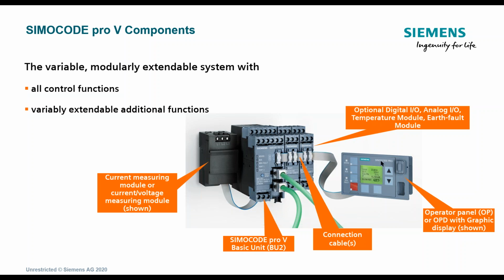Okay. One thing I want to talk about is the operator panel. This is your fluke meter, guys. If we mounted this in a motor control center bucket, and this is on the door, this little operator panel can tell you more than any fluke meter can tell you. If you opened up the MCC door and started probing inside of it, this will tell you how many times the motor's turned on and off. It could tell you how many times the motor's been running. This will show you up to 20 trips with a time and date stamp. The 21st trip would just be the one that's active.